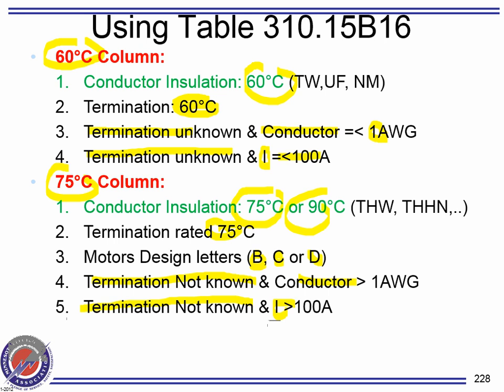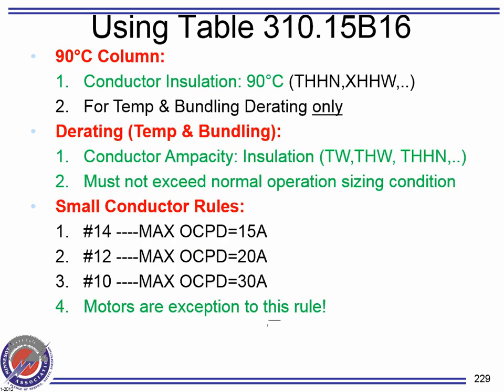Okay, 90. When would I use 90? The only time you use 90 is if your installation is rated for 90. Otherwise, don't think about it. And what do we use it for? Do we use it to size under normal operating conditions? No. You always use it to what? Derate. Okay. So you use it only to derate.